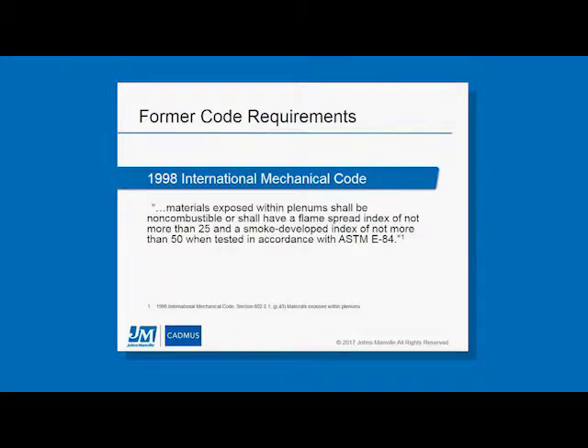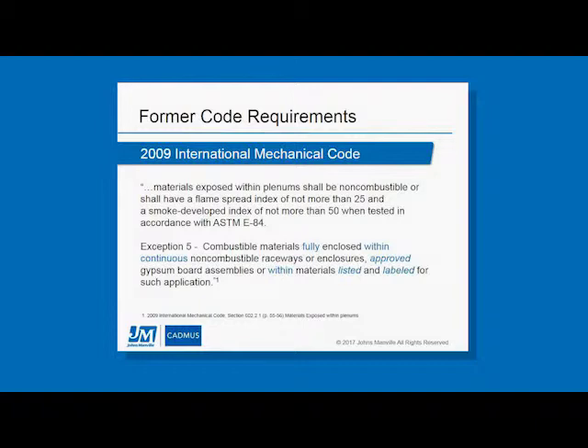In 1998, the International Mechanical Code had very straightforward language as far as materials and what was required of those materials in a plenum space. The definition here states that the materials either needed to be non-combustible or have a fire hazard classification rating of a 25 or less flame spread index and a smoke developed index of not greater than 50 when tested according to ASTM E84. And this fire hazard classification is something that you will see in the International Mechanical Code for sure.